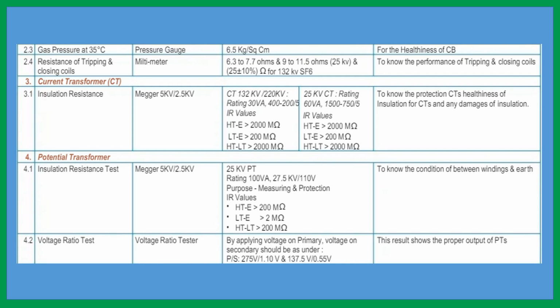Now the question is why the volt ampere has been raised. Because the voltage is low and the current is more, and the conductor size mainly depends on the current. You know I square RT by J is the formula. So current is squared, and it will produce more heat. If the current is more, it will affect more than voltage. So we have to raise the volt ampere. It is 60 volt ampere.